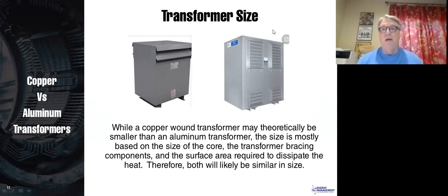Now, transformer size, there's no doubt that a coil can be built smaller with copper versus with aluminum, but size is typically not based so much on the coil size. It may be based on the geometry of the coil. In other words, is it round versus rectangular, how tightly packed those coils are. It's based upon the bracing. If you look inside of a transformer, you typically have some big steel braces that try to keep that transformer tight and help it withstand short circuits. And it's built on the heat withstand.